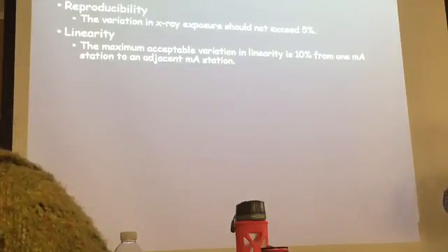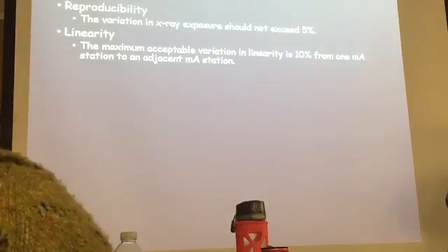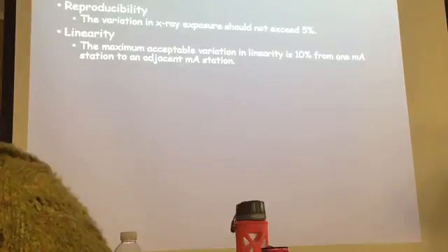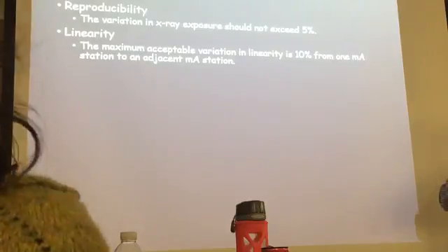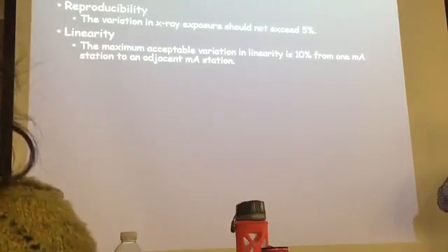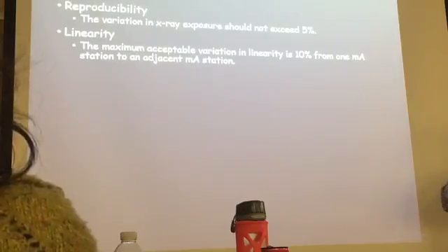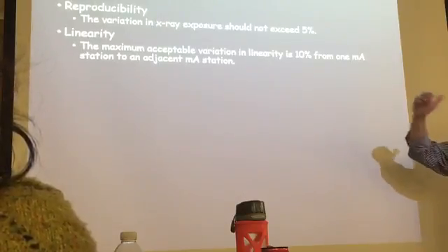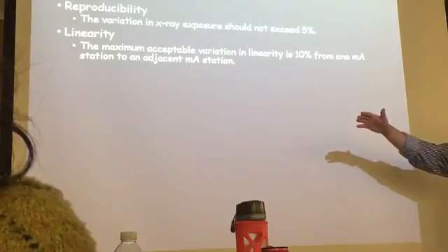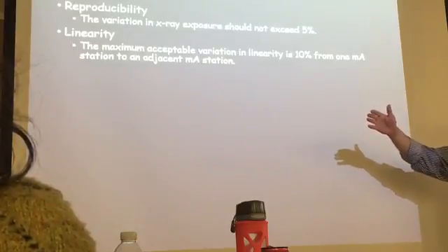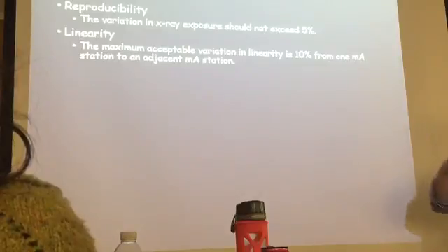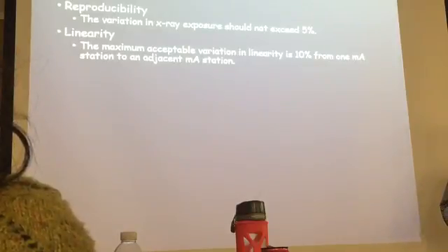When you measure exposure time and you're getting very close to milliseconds, say 5 milliseconds, 1 millisecond, you might not get exactly what you want. And the same thing happens when your exposure is very high, 3 seconds of exposure. You don't get what you want, and so you need to check that.